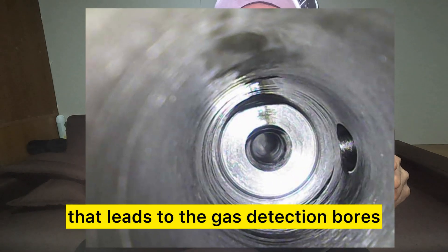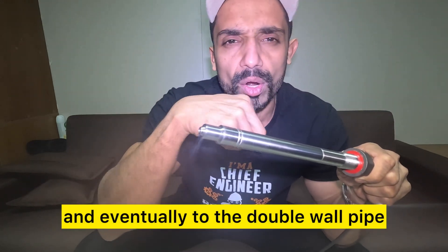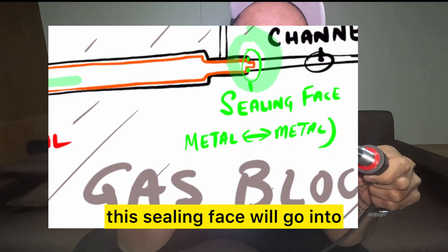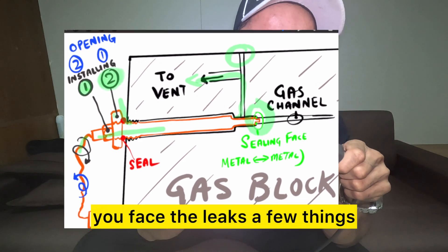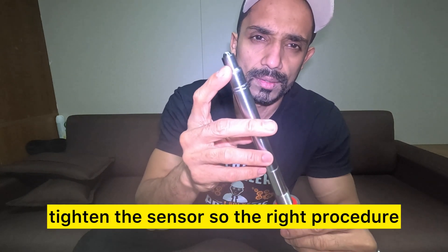In between there is a small bore that leads to the gas detection bores and eventually to the double wall pipe and out to the vent. Any leaks at this sealing face will go into that bore and out into the vent. In case you face leaks, a few things: when you take off the sensor you can also tighten the sensor.